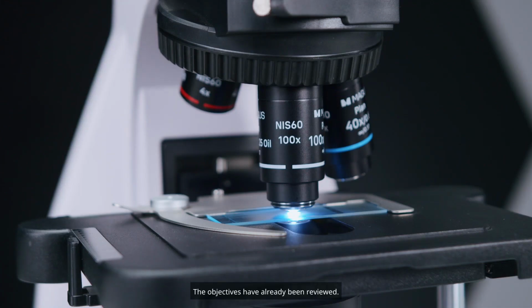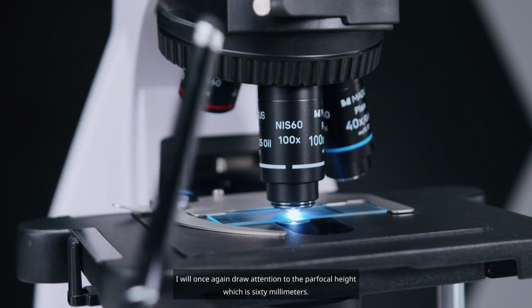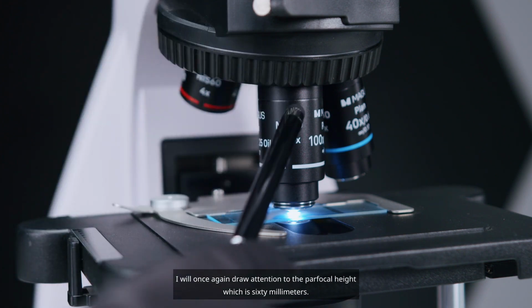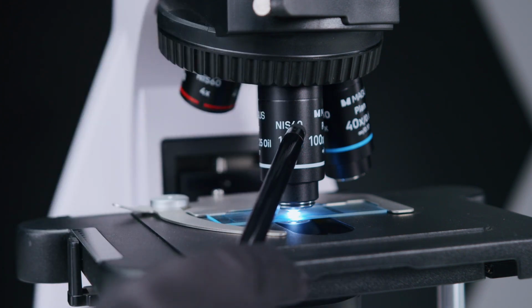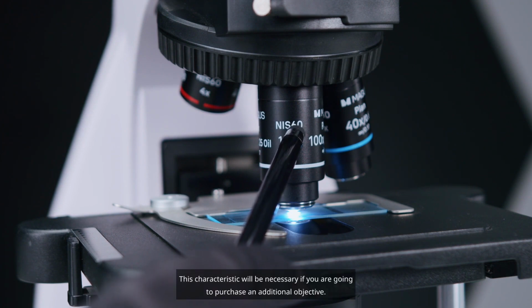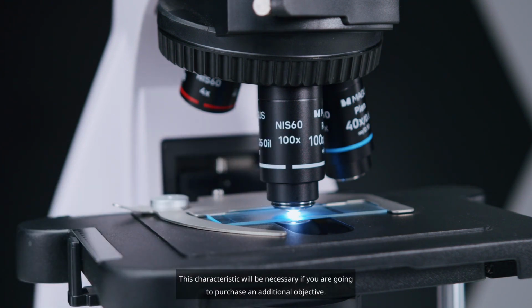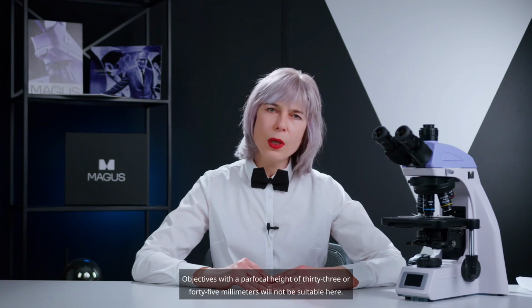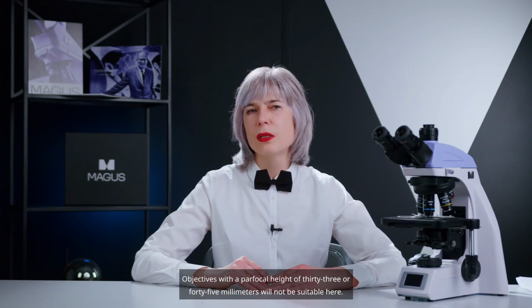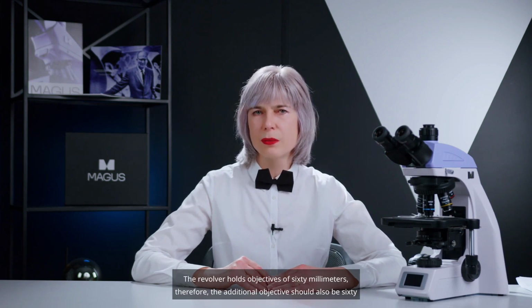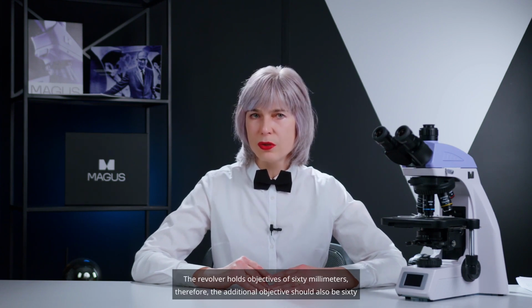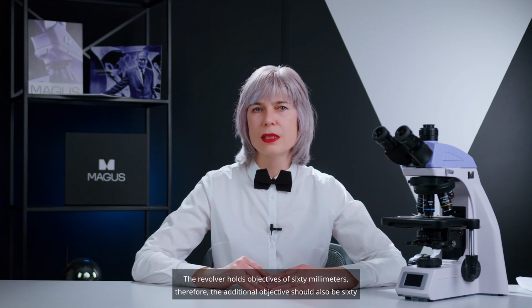The objectives have already been reviewed. I will once again draw attention to the parfocal height, which is 60 millimeters. This characteristic will be necessary if you are going to purchase an additional objective. Objectives with a parfocal height of 33 or 45 millimeters will not be suitable here. The revolver holds objectives of 60 millimeters. Therefore, the additional objective should also be 60 millimeters. The stage.